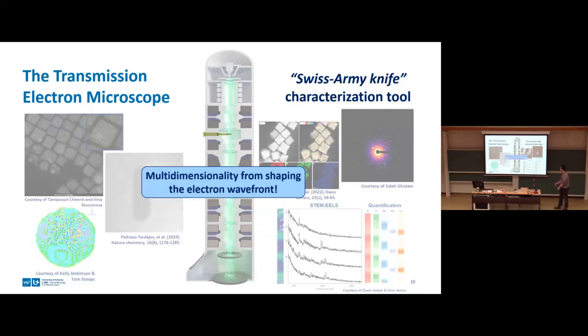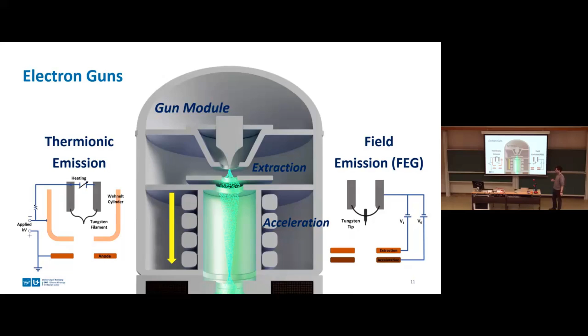At the gun module, we'll find a tungsten material from which we extract electrons. And those electrons are going to be accelerated towards the optical column in the microscope. And for more specificity, in the beginning, we started with thermionic emission guns that are more or less similar to what you see in an incandescent bulb, where a filament is heated up. From that filament, you see light, but you can also get electron emission. But nowadays, we have brighter and better sources in the form of field emission guns. Now what we do is create a field, and due to the field, we lower the potential barrier of the material and have tunnel emission to the microscope.